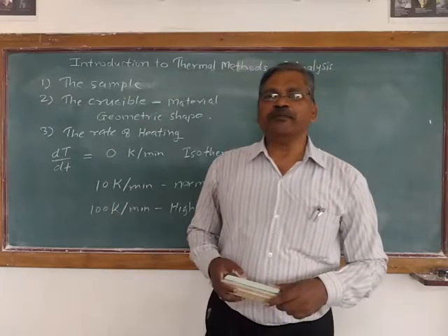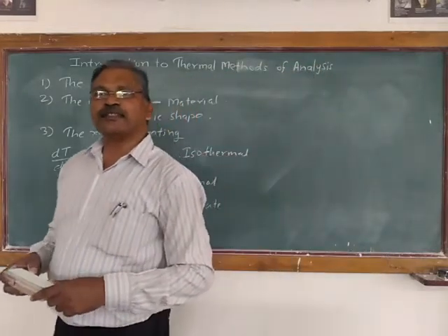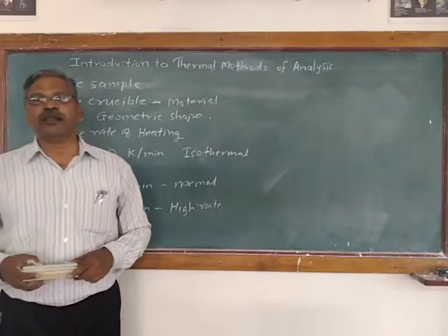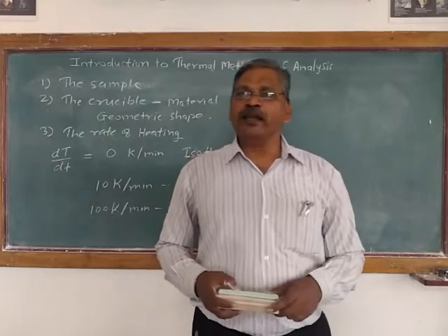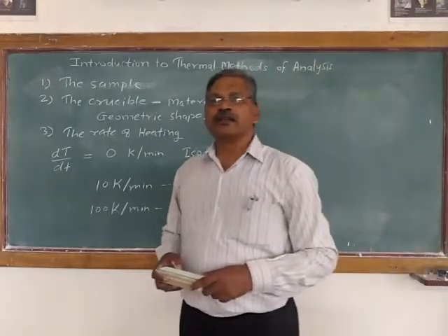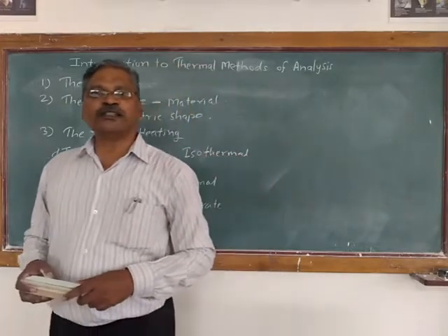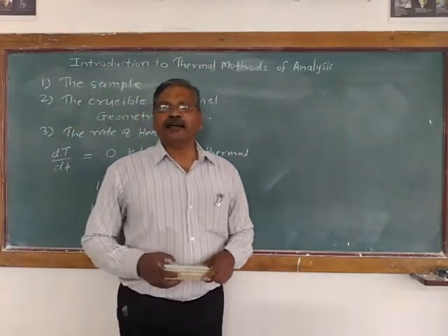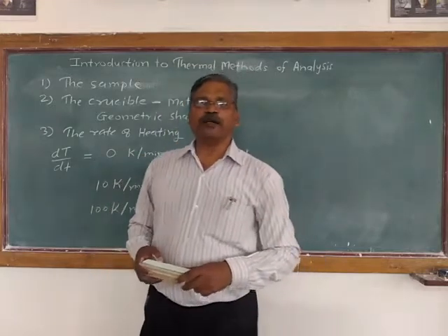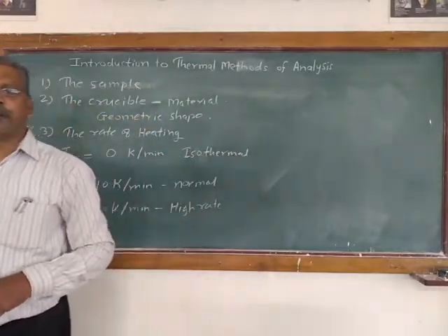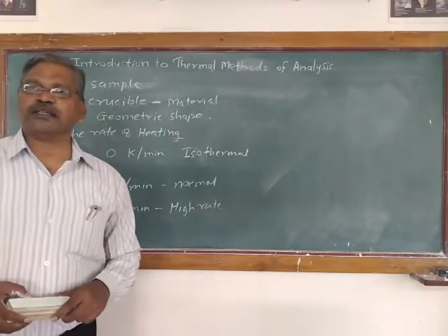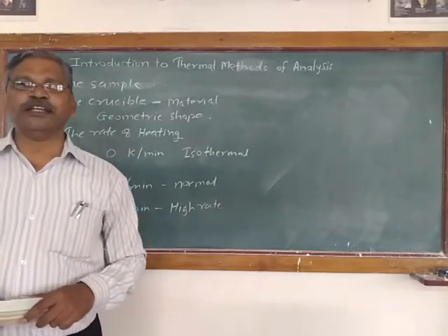The transfer of heat between the source, such as the furnace, and the different parts of the sample or reference material is not instantaneous, but will depend on conditions like conduction, convection, and radiation that occur within the apparatus. There is bound to be thermal lag between different parts of the apparatus, and the higher the rate of heating, the greater the lag will be.